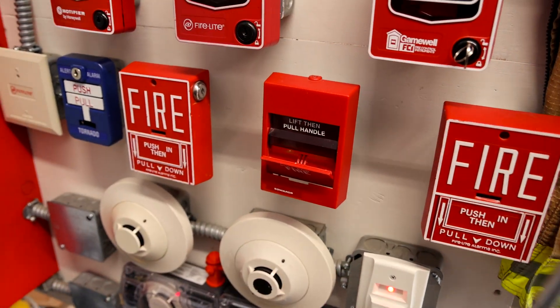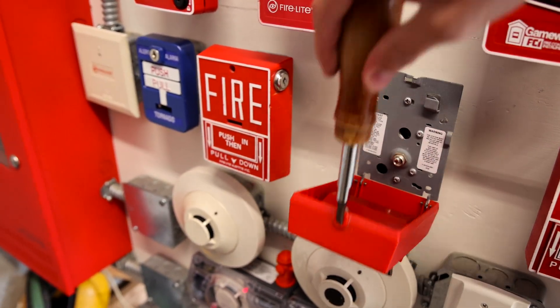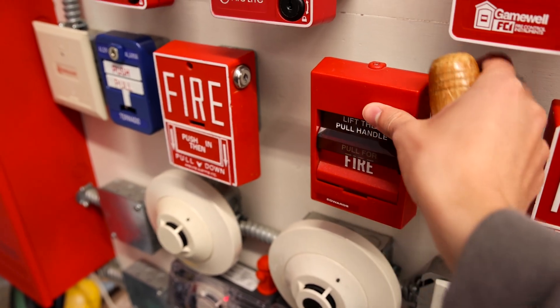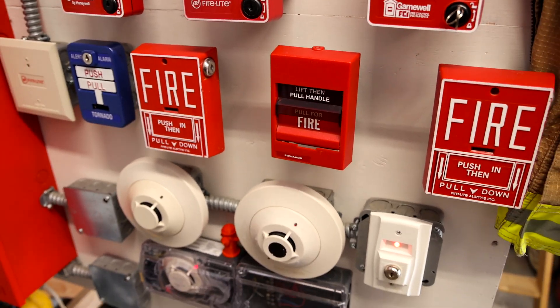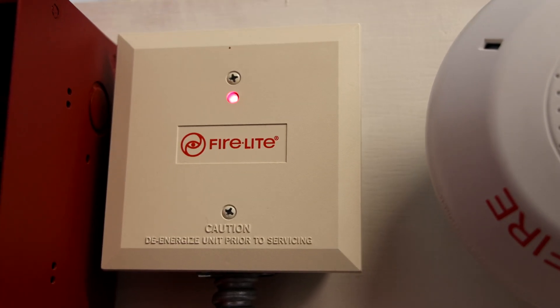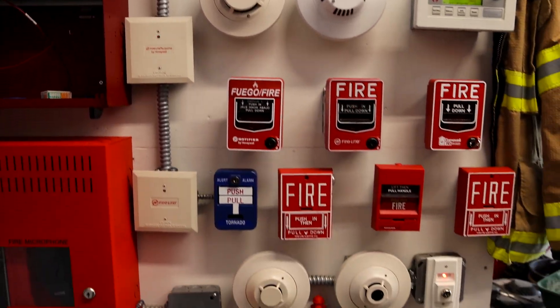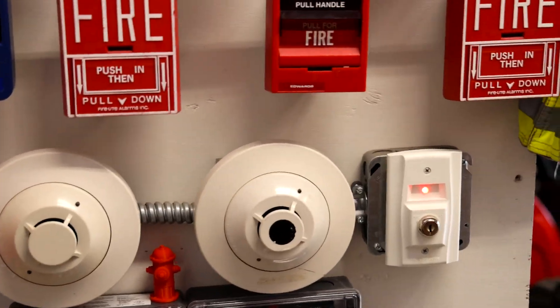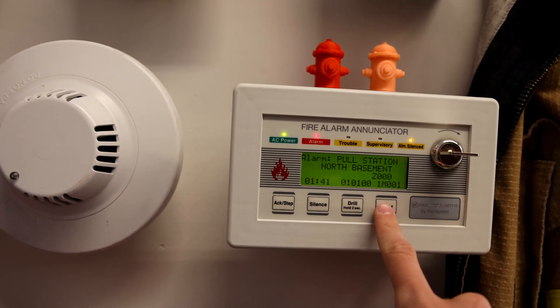Let's reset the pull station and then I'll show you that new thing with the tornado alarm. There we go. And then also up here is what it looks like when the monitor module gets activated, because this one is wired into that duct detector key switch down below. All right, we'll go ahead and give the entire fire alarm system a reset. There we go.